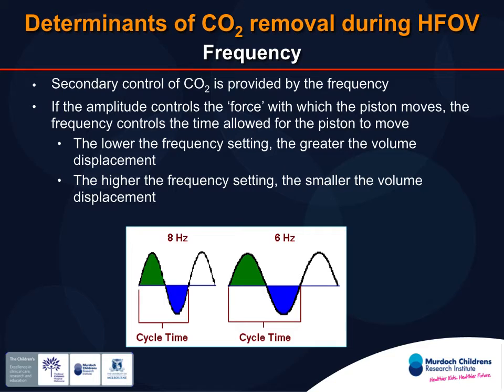The other important thing to bear in mind is that, unlike a conventional ventilator and unlike the jet, there is an interrelationship. We don't set an I time and an E time. We set the frequency, the number of respiratory cycles per minute, and we set the percentage of time you'll be in inspiration and expiration. So if you have a 1-to-1 ratio, you're asking for just as much time in inspiration as in expiration. If you have a 1-to-2, you're asking the lung to have twice as much time for expiration as it would in inspiration.